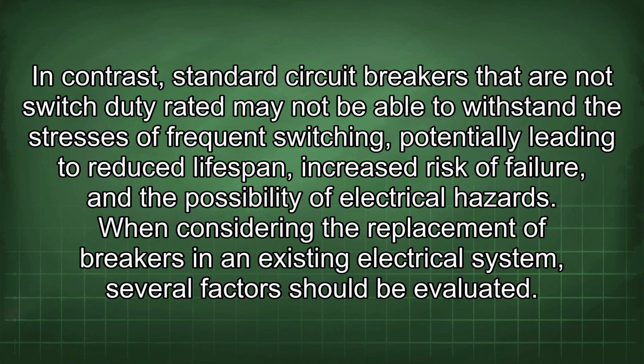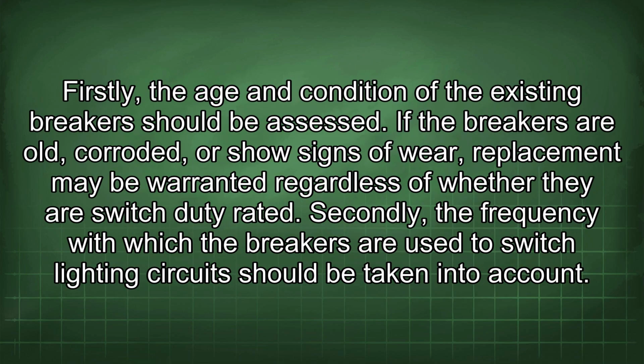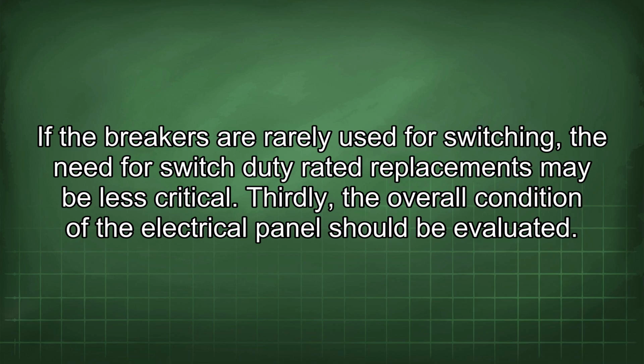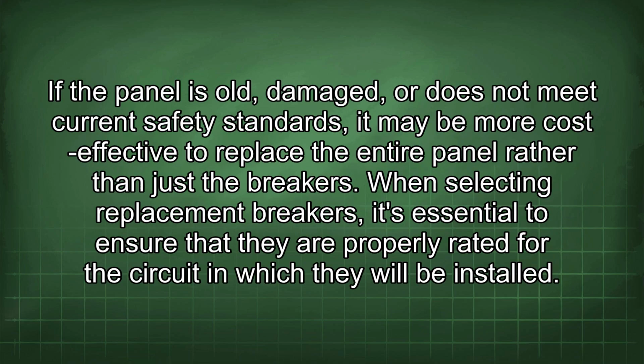When considering the replacement of breakers in an existing electrical system, several factors should be evaluated. Firstly, the age and condition of the existing breaker should be assessed. If the breakers are old, corroded, or show signs of wear, replacement may be warranted regardless of whether they are switch duty rated. Secondly, the frequency with which the breakers are used to switch lighting circuits should be taken into account. If the breakers are rarely used for switching, the need for switch duty rated replacements may be less critical. Thirdly, the overall condition of the electrical panel should be evaluated. If the panel is old, damaged, or does not meet current safety standards, it may be more cost-effective to replace the entire panel rather than just the breakers.